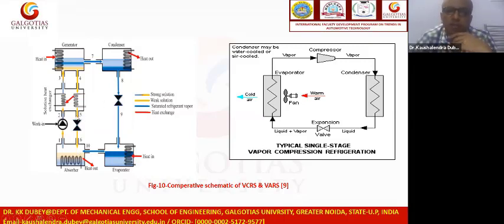If we take the lithium bromide water solution, water is the refrigerant and lithium bromide is the absorbent. These are chemically soluble in each other. Here the refrigerant will mix with the water, and it makes the rich solution of the absorbent and refrigerant. Now this pump pumps the rich solution and provides the required pressure for this cooling system. Here the pressurized rich solution is passing through this heat exchanger.